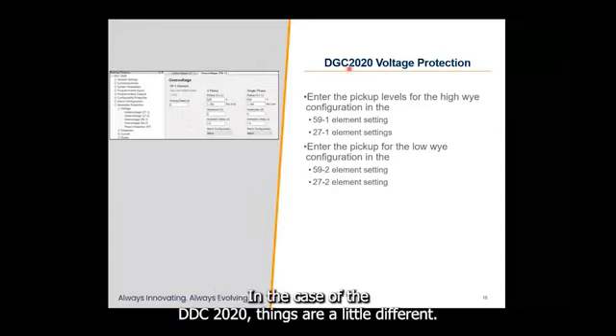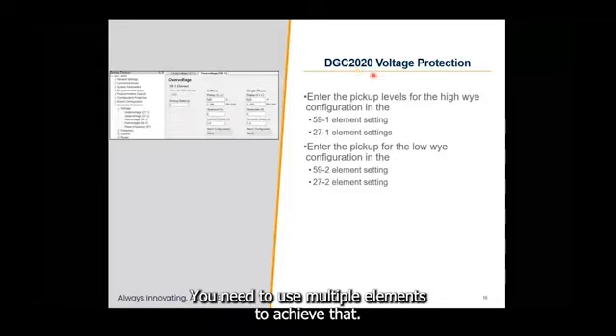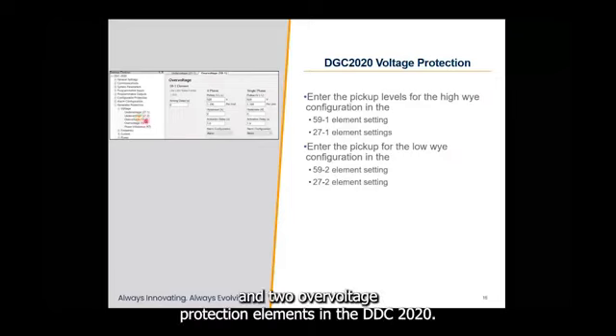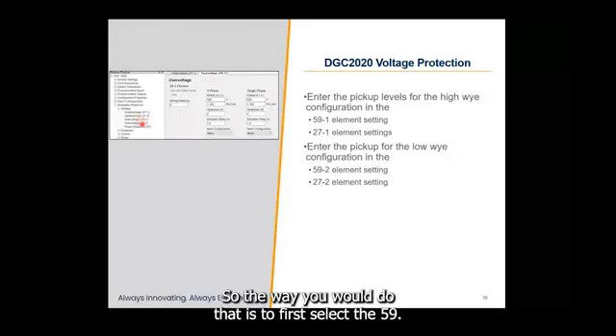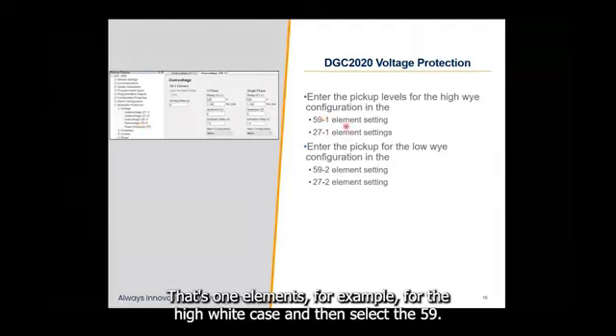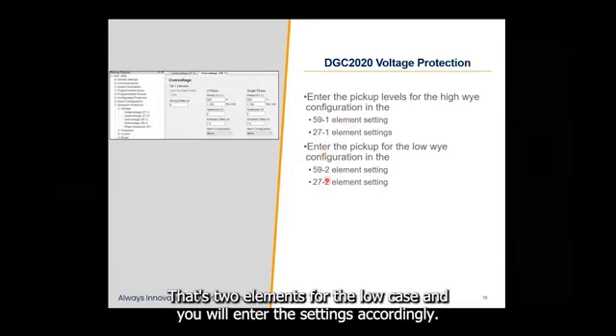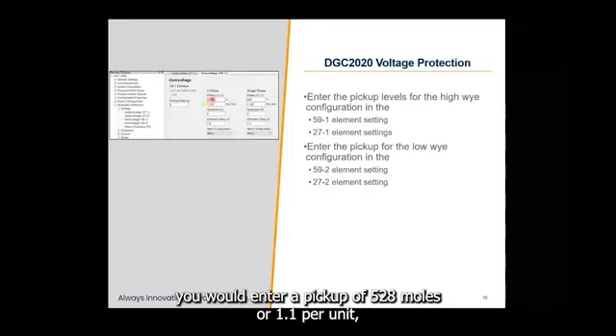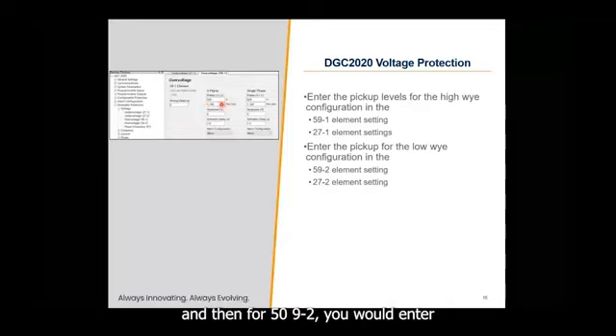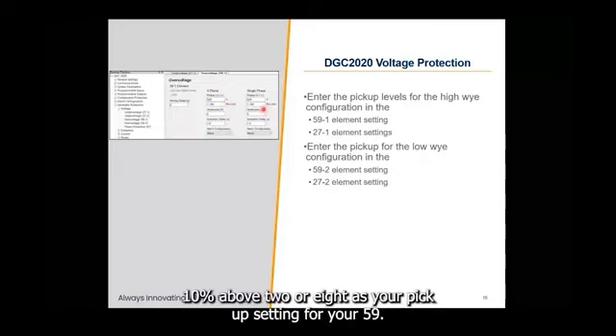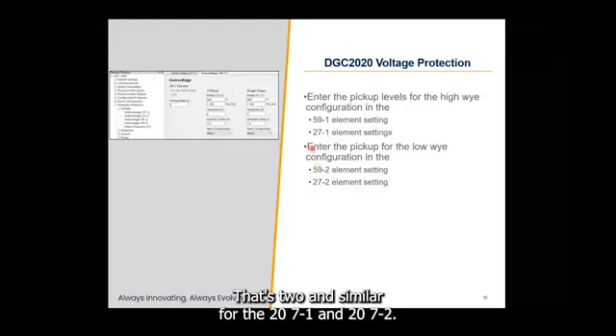In the case of the DGC 2020, things are a little different. You need to use multiple elements to achieve that. There are 2 under voltage protection elements and 2 over voltage protection elements in the DGC 2020. So the way you would do that is to first select the 59-1 elements, for example, for the high Y case, and then select the 59-2 elements for the low Y case. And you would enter the settings accordingly. So here for your 59-1, that's your high Y case, you would enter a pickup of 528 volts or 1.1 per unit. And then for 59-2, you would enter 10% above 208 as your pickup setting, and similar for the 27-1 and 27-2.